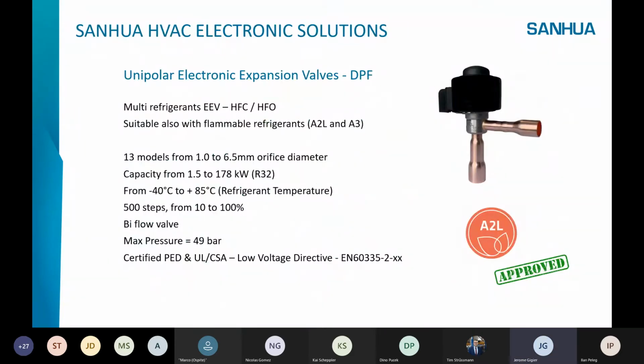So I'm going to start with the unipolar electronic expansion valve. The name is DPF. DPF is a unipolar valve, suitable with all the refrigerants on the market, even for A2L and A3 refrigerants. We have 13 models from very small orifice, 1.0, to 6.5 millimeters. This corresponds to a capacity of around 1 kilowatt to 180 kilowatt for R32. The temperature range is huge, minus 40 to 85 degrees. This valve has 500 steps from 10 to 100%, so you can open it from 10 to 100%.